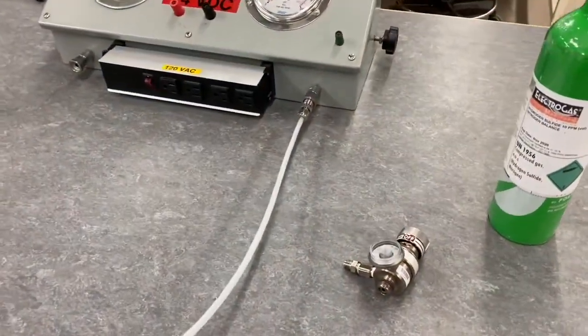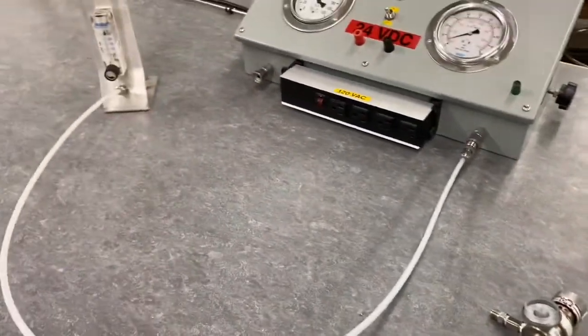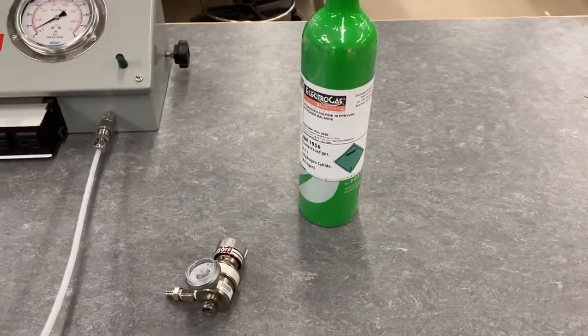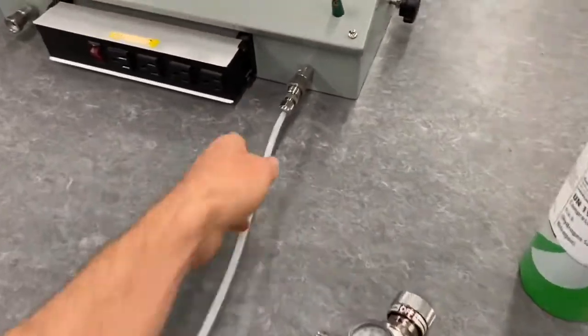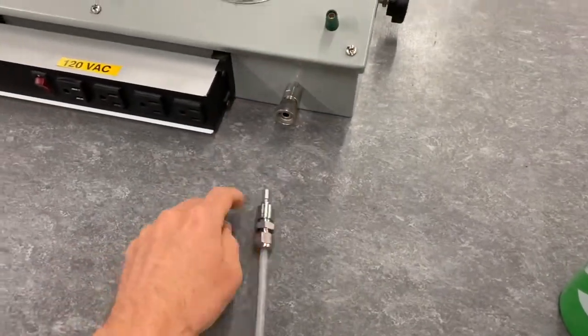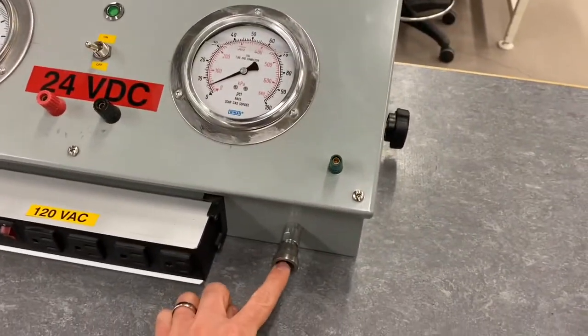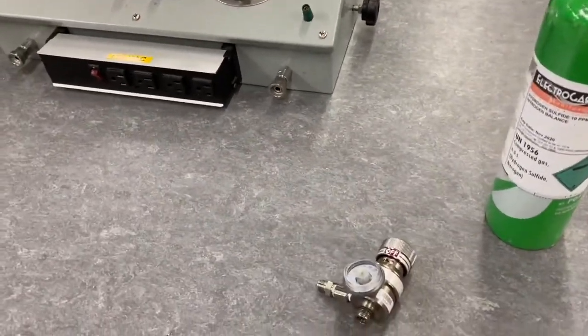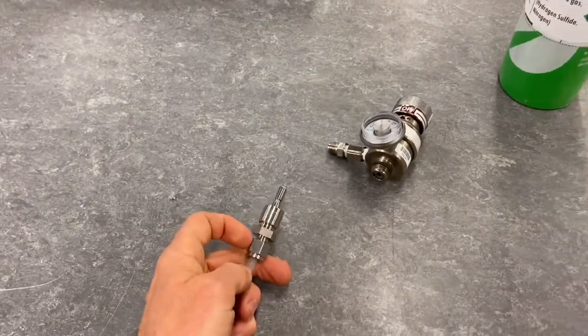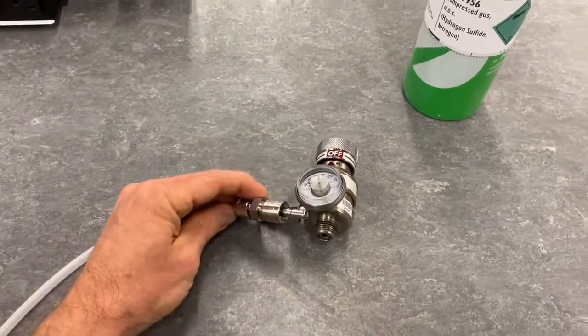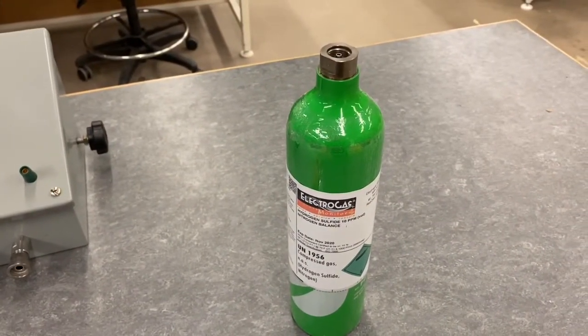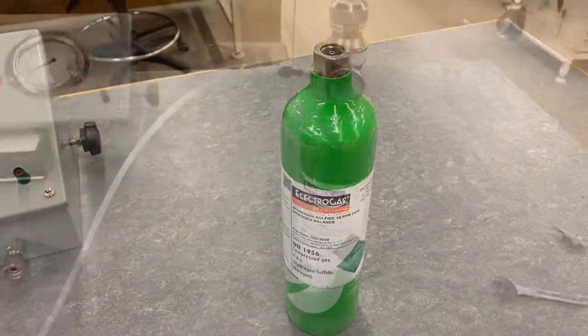When I want to run the toxic gas, the H2S, we can just remove this. We can even leave the pressure on. You can see these quick connect things have a valve in them. We can just pop them out like that. Then I can take the fitting off and connect it to our regulator and put it on our calibration gas bottle and introduce 10 ppm H2S to the sensor.